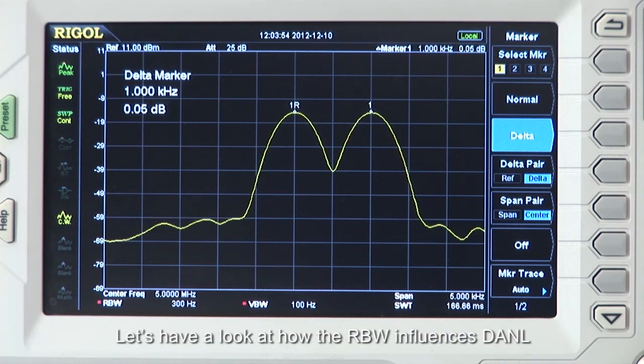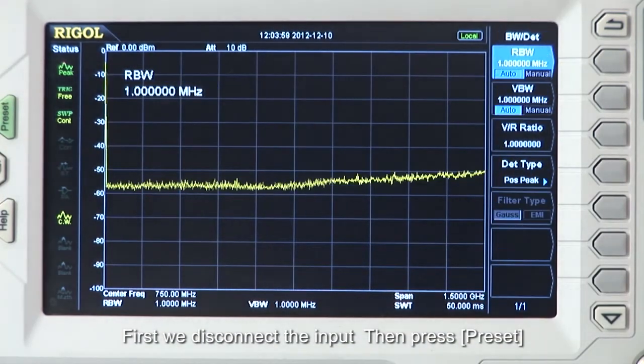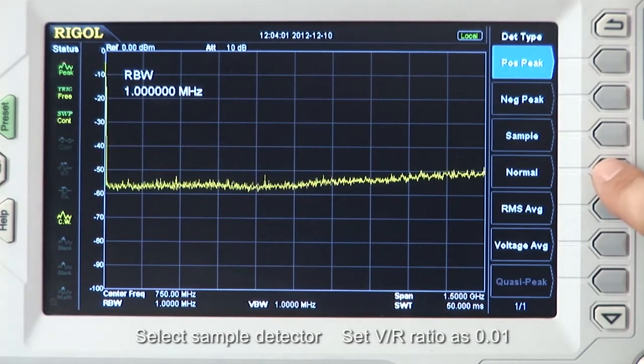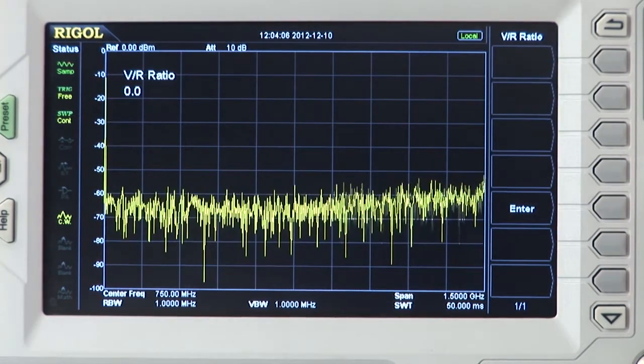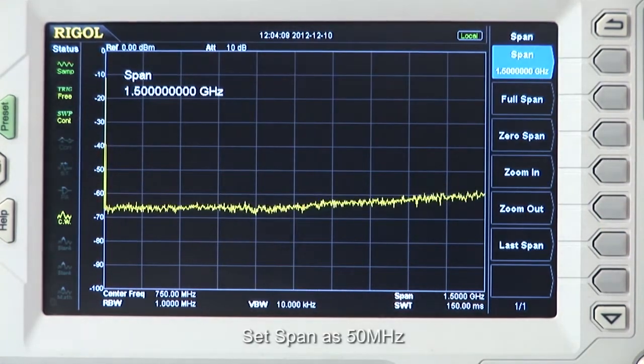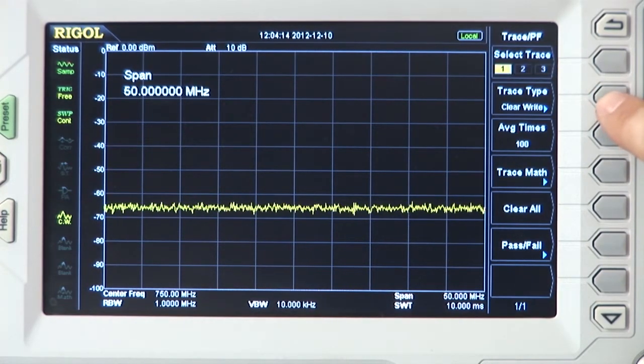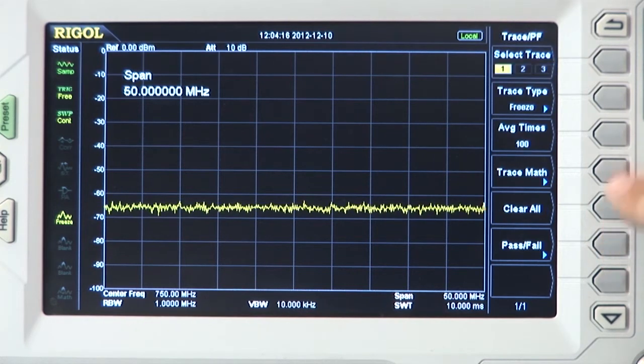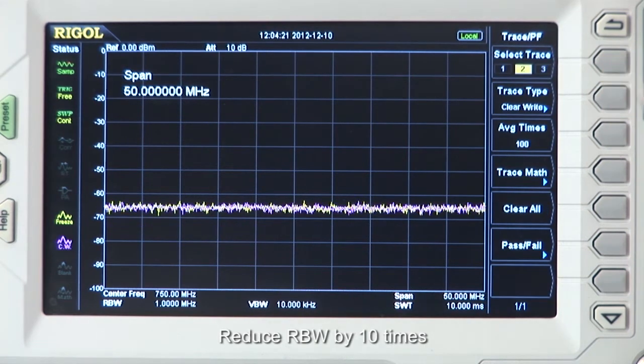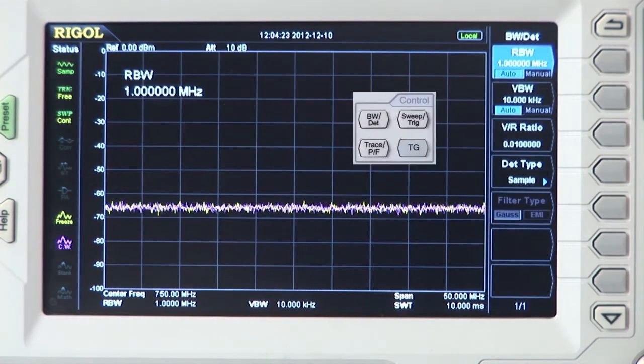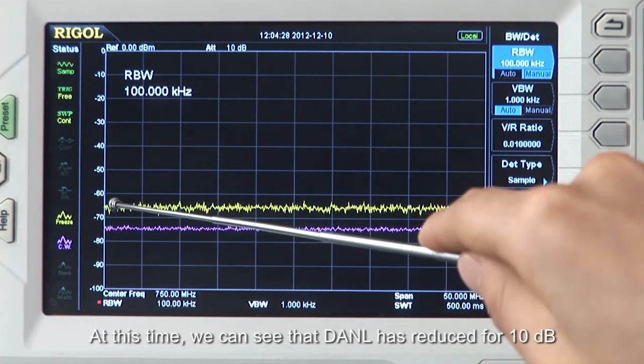Let's have a look at how the RBW influences DANL. First we disconnect the input, then press Preset, select Sample Detector, set V to R ratio as 0.01, set the span as 50 MHz, hold the trace, and enable trace 2. Now let's reduce the RBW by 10x, and at this time we can see the DANL has reduced 10 dB.